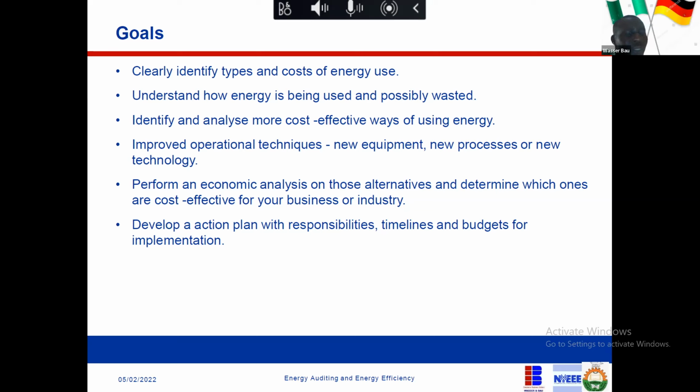You can be asking somebody who uses a heating system. Like I know an audit where I went to a kitchen in a hotel, and the person in the kitchen told me that the water heater is on 24 hours a day. Yes. That anytime they need hot water, they just go and turn it on and take hot water. And the heater is 24 hours on. And I can see, okay, it has a thermostat here. It's okay. Thermostat is okay, right? Yeah, it has a thermostat, but that's not enough, because heating is one of the areas energy is always wasted.